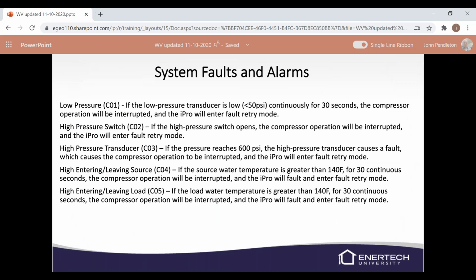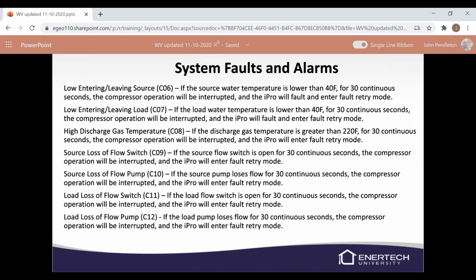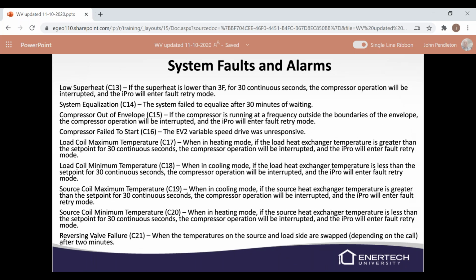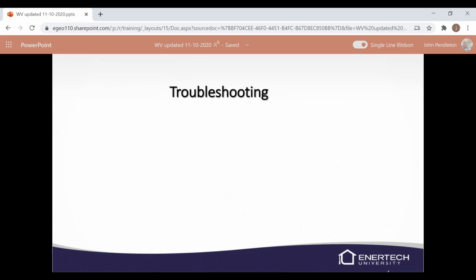You can see these are some of the different faults and alarms. We have low pressure, high pressure, those are switches, transducers, high entering, leaving load and source water temperatures. I'm not going to get really into a lot of these today. These are all listed in the IOM. And also you can go right to the screen on the HMI and it'll tell you. But again, we have like 20 some different faults here. Compressor running out of envelope, source coil minimum temperature has been reached, things like that. There's also drive faults and probe faults. You can also scroll through those. Those don't happen real often.